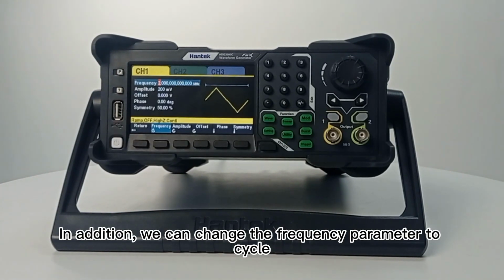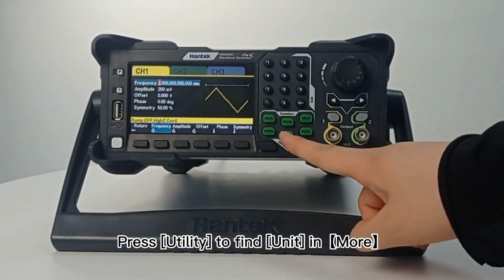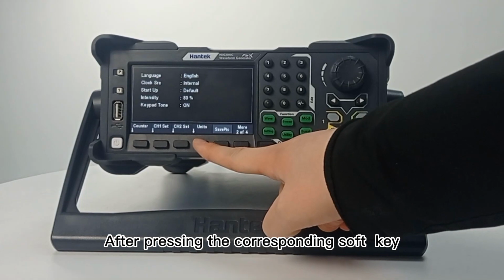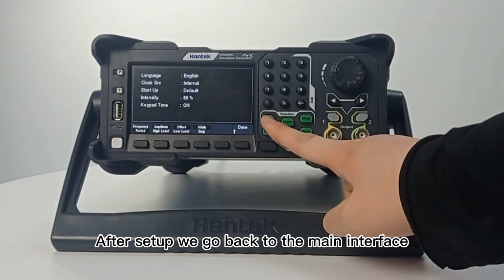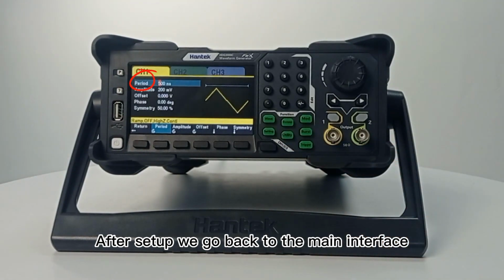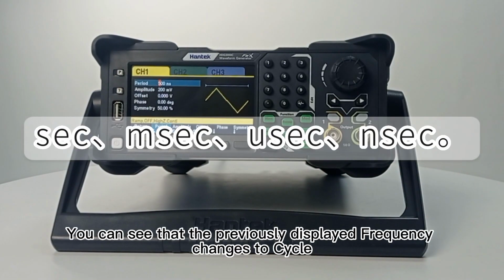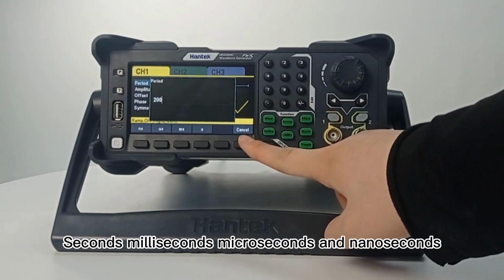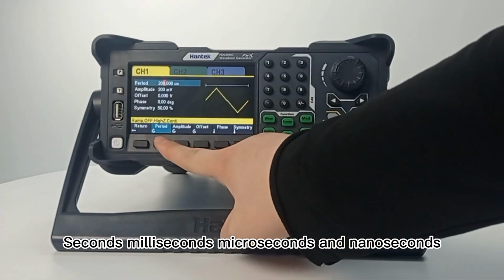In addition, we can change the frequency parameter to period. Press Utility to find Unit in More. After pressing the corresponding soft key, you can switch the frequency parameter to period. After setup, we go back to the main interface. You can see that the previously displayed frequency changes to period. Optional period units are seconds, milliseconds, microseconds, and nanoseconds.